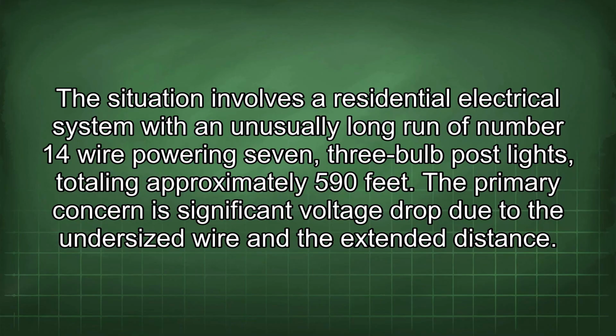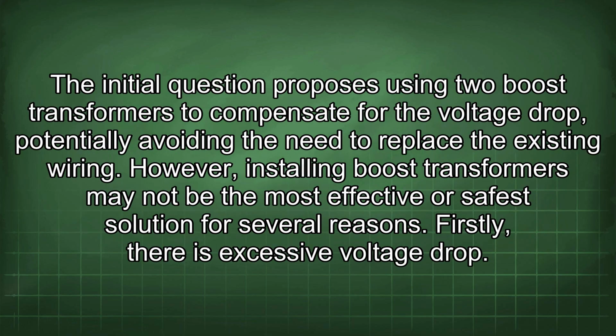This situation involves a residential electrical system with an unusually long run of number 14 wire powering seven, 3 bulb post lights, totaling approximately 590 feet. The primary concern is significant voltage drop due to the undersized wire and the extended distance. The initial question proposes using 2 boost transformers to compensate for the voltage drop, potentially avoiding the need to replace the existing wiring. However, installing boost transformers may not be the most effective or safest solution for several reasons.